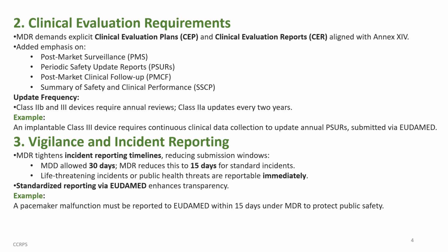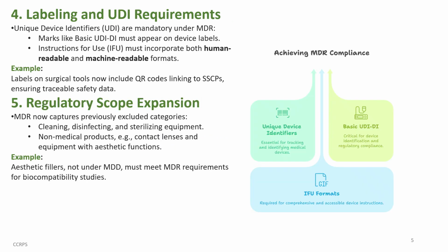Vigilance and incident reporting. MDR tightens incident reporting timelines, reducing submission windows. MDD allows 30 days. MDR reduces this to 15 days for standard incidents. Life-threatening incidents or public health threats are reportable immediately. Standardized reporting via EUDAMED enhances transparency. Example: a pacemaker malfunction must be reported to EUDAMED within 15 days under MDR to protect public safety.